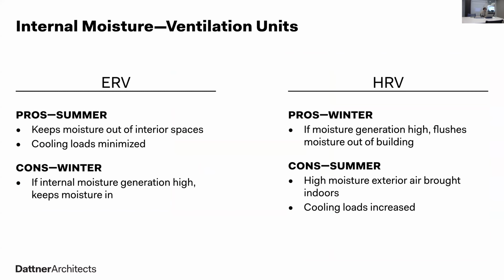So one of the design considerations that we had to look closely at was whether to use ERVs or HRVs. And we did end up with ERVs, basically to minimize our cooling loads and keep humidity down in the summer.